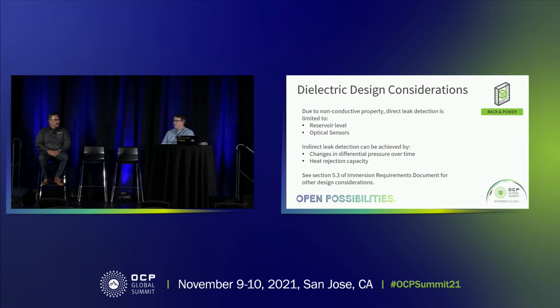And as Fred said, probably one of the biggest things is when there's a leak and things aren't running to the design point, you'll see a heat rejection capacity reduction. And it's being able to monitor that and say, well, did nodes come offline? Is the workload just low? Or do I actually have a deficiency in my cooling loop that I need to investigate further?